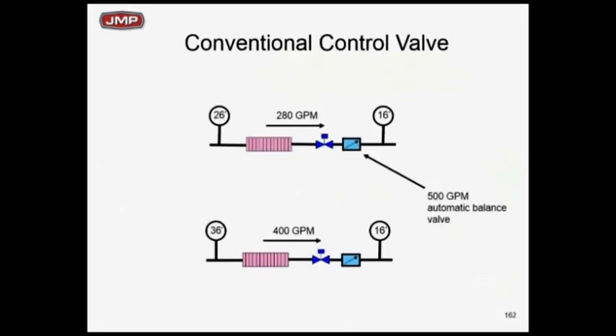Like I said, one of my pet peeves is people telling me, you just put a two-way valve in series with a flow limiter, you can do the same thing. Let's make sure you understand that's an outright lie. It's just not true. Why is it not true? I've got my situation. This is a 500 GPM coil. So if you have a 500 GPM coil, at what flow rate do you have to pick your flow limiter? 500. So I put a 500 GPM flow limiter in series with my two-way valve.